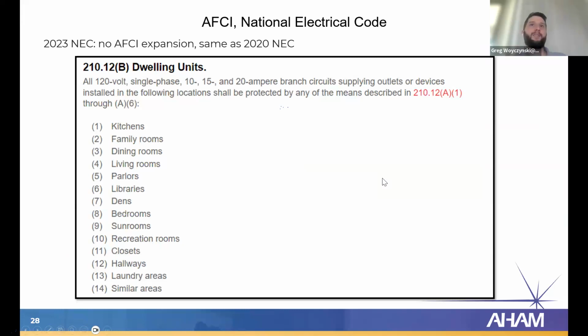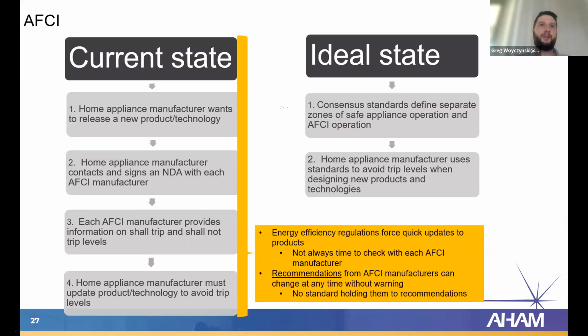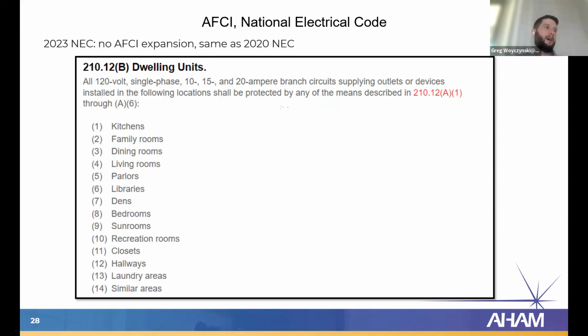Some good news on AFCIs is we have not seen AFCI expansion in the electrical codes recently. In the 2023 NEC, we saw no expansion of AFCI. So when it comes to AFCIs, the 2020 NEC and the 2023 NEC are in alignment. And it's the reason AFCI manufacturers weren't able to achieve that expansion are because of these reasons.